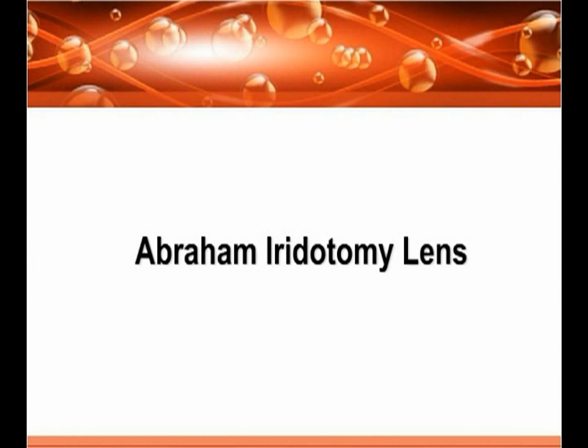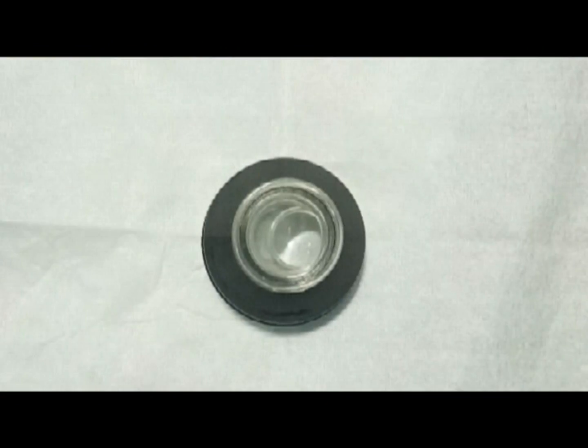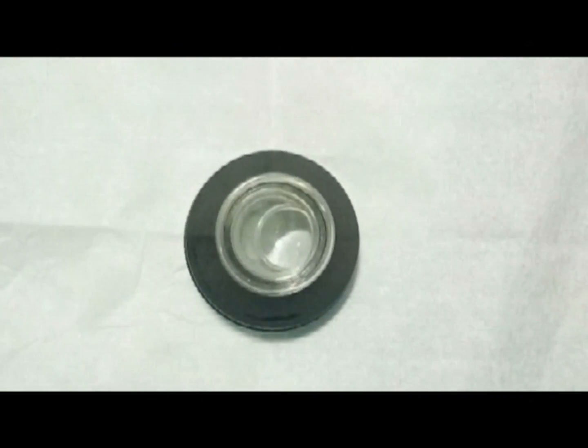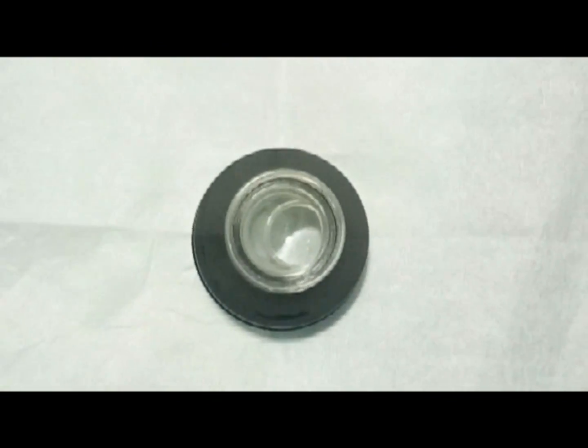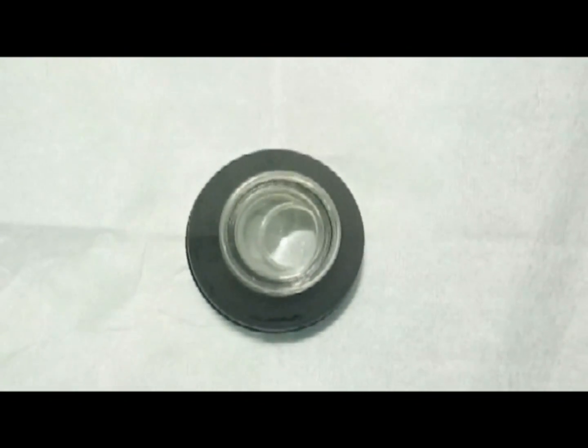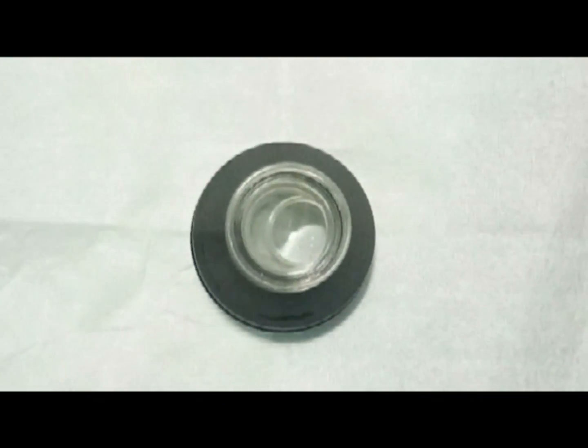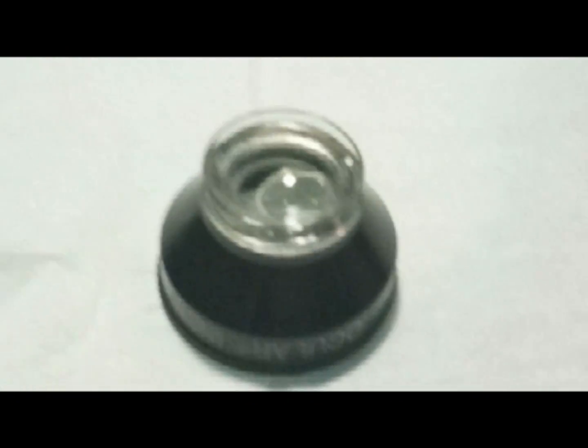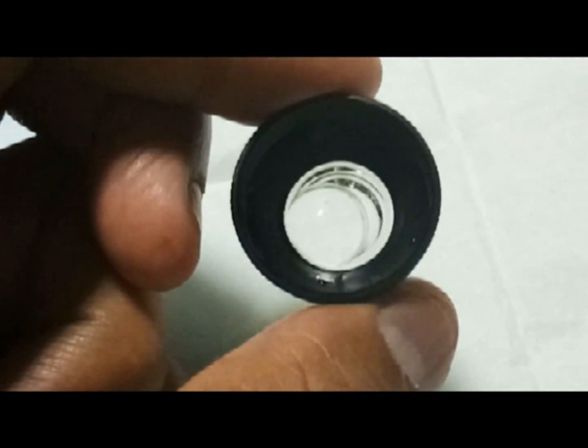The laser energy is concentrated at the level of the iris, the number of corneal epithelial burns is minimized, and the lens keeps the eye open. This lens is a plus 66 diopter plano-convex button bonded into a decentered 8mm hole. Here we can see the Abraham Iridotomy lens.